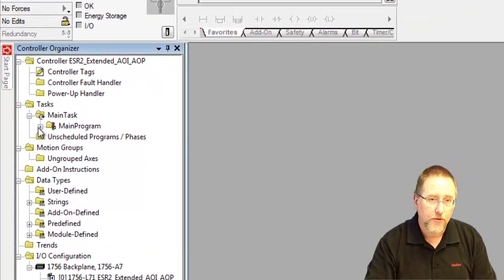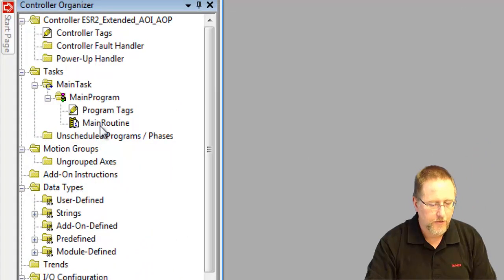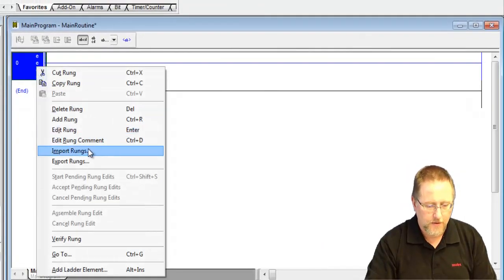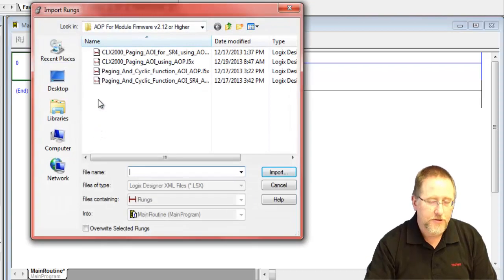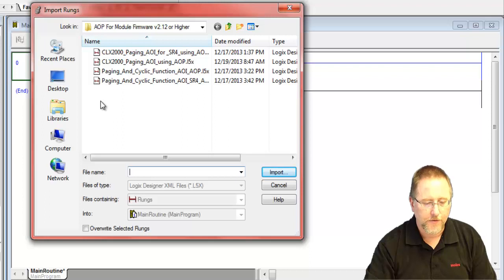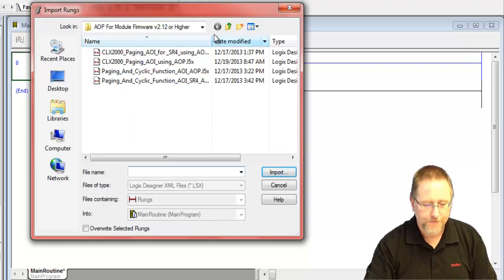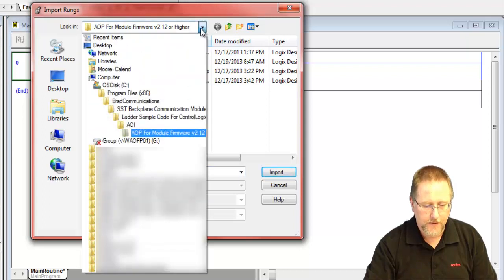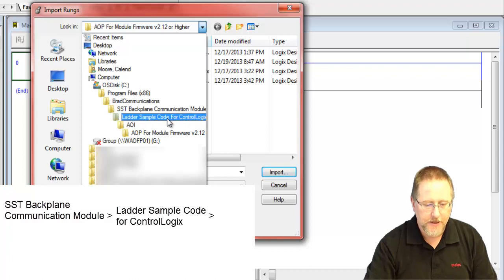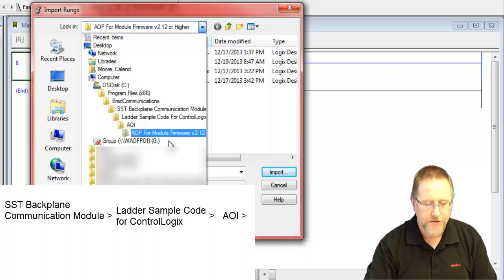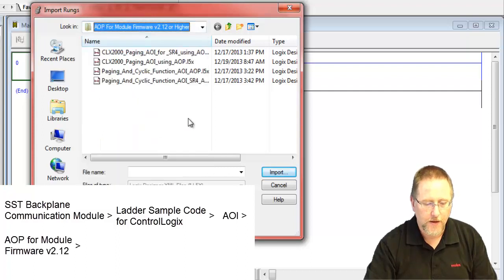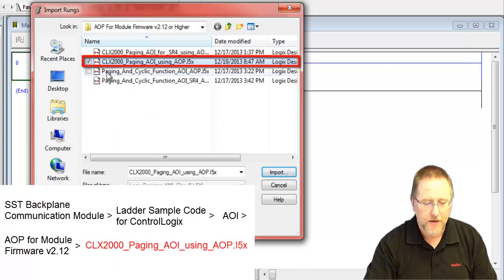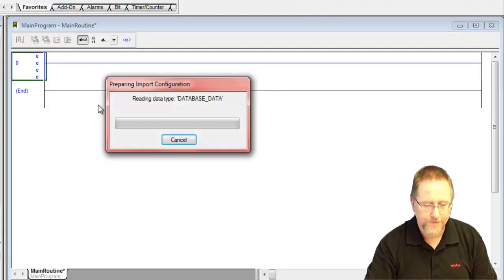Now we need to import the add-on instruction. So we go to our main routine and import rungs. The add-on instructions get installed when you install the software. So you'll find that under program files and then BRAD communications and SST Backplane Communication Module, ladder sample, AOI for add-on instructions, and AOP for module firmware 2.12. So the one we want is the CLX 2000 paging AOI using AOP. We import that.